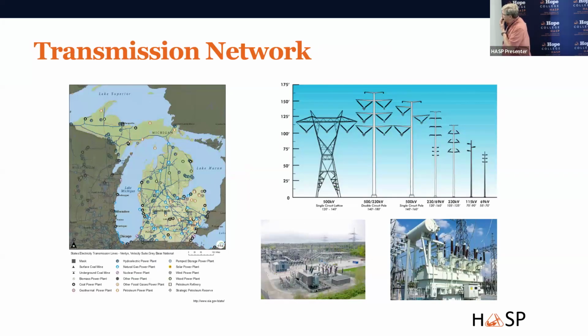A little bit about the transmission network. So you can see a map of the transmission network in Michigan. And in the upper right is a diagram showing that if you're driving around and you see power poles, you can tell how much voltage is in general by their design. On the far left, the lattice-type architecture, those are typically 345,000 volts up to about 750,000. Typically they don't go above 750,000, and that you'd see around a large city like Chicago, Detroit, or Cleveland.